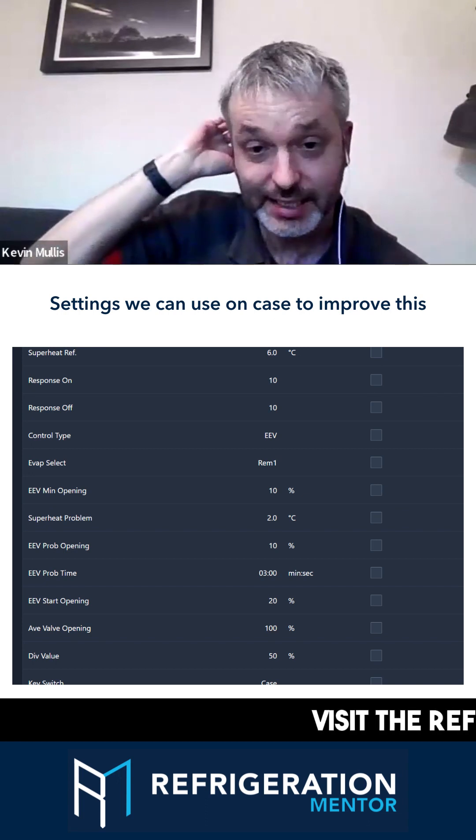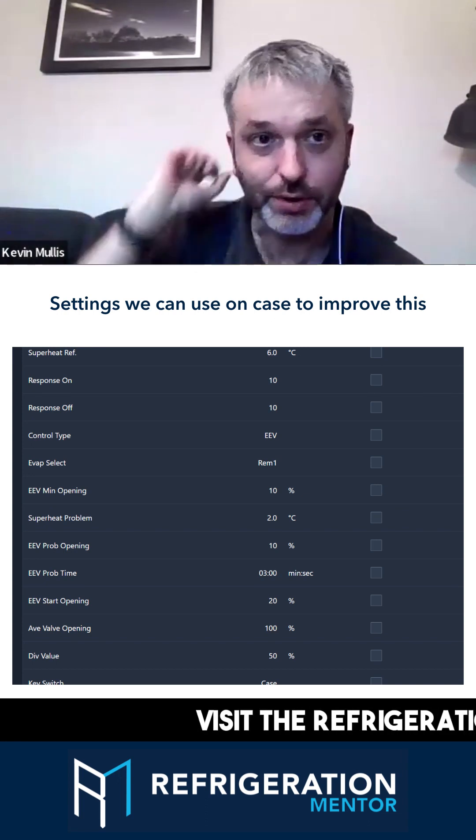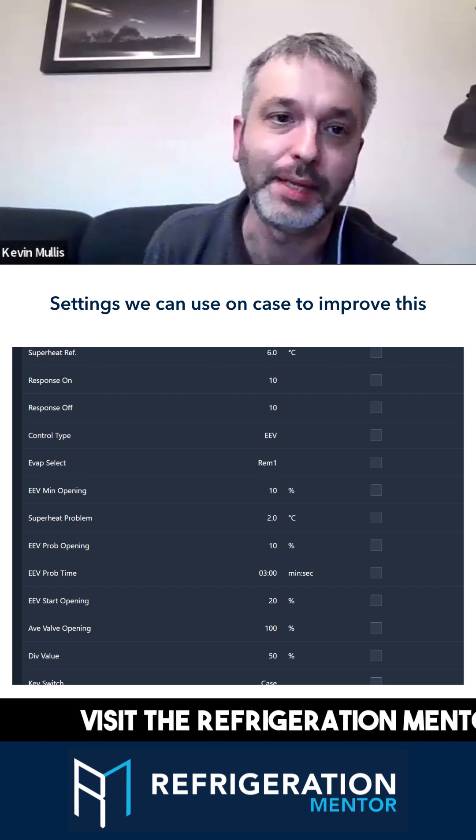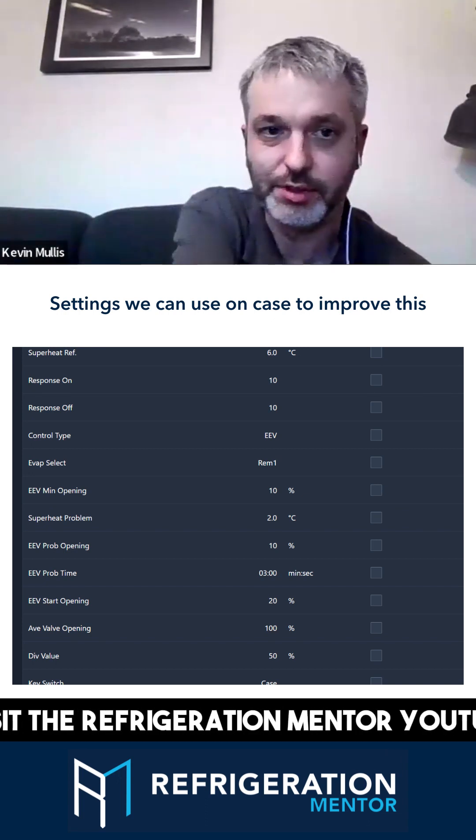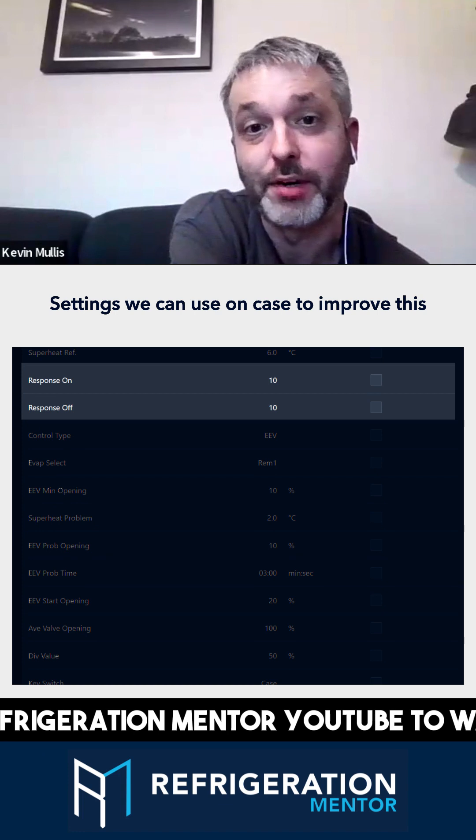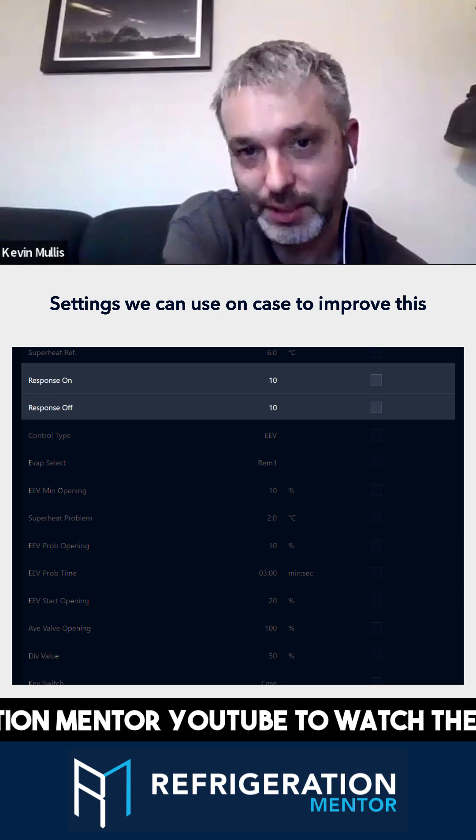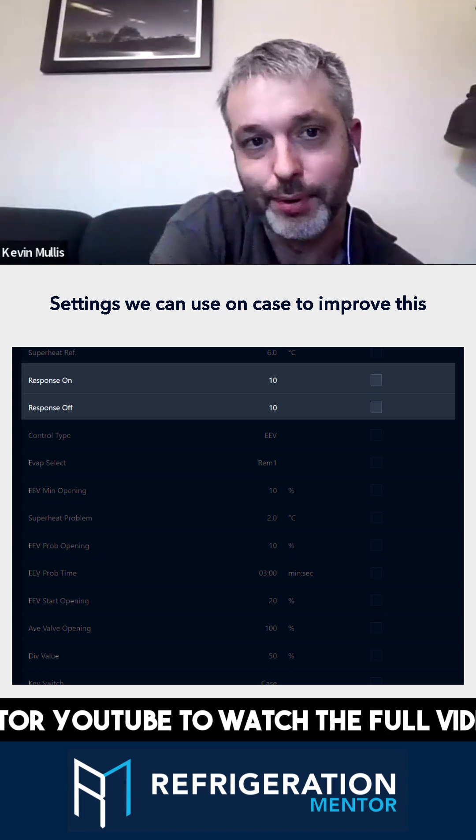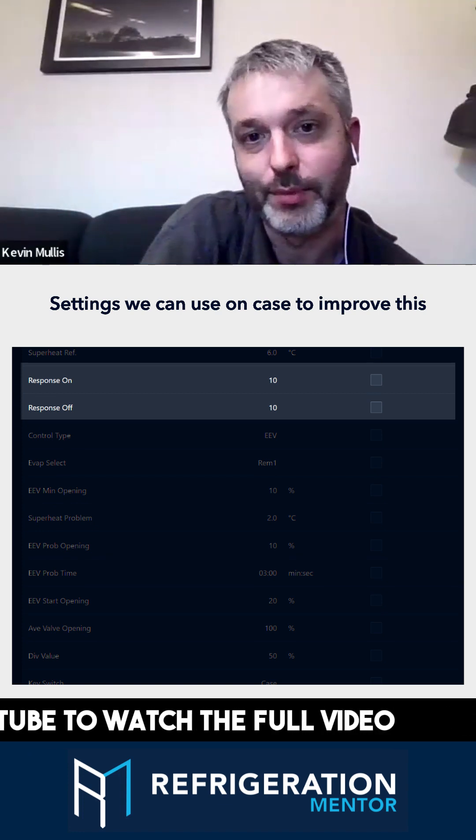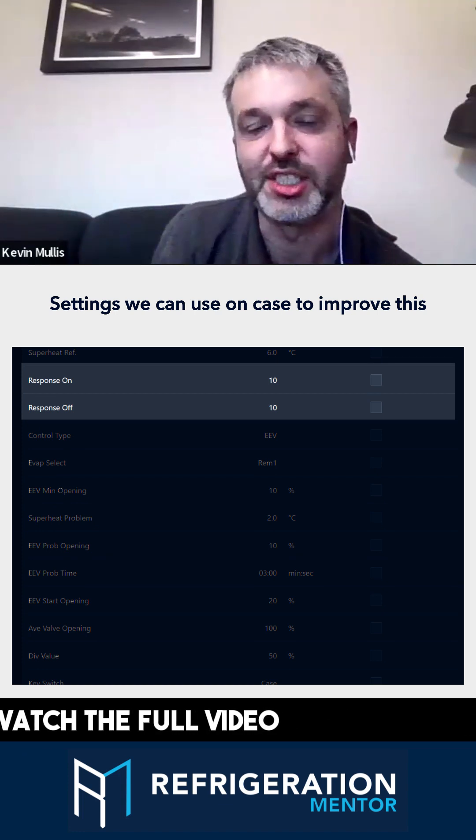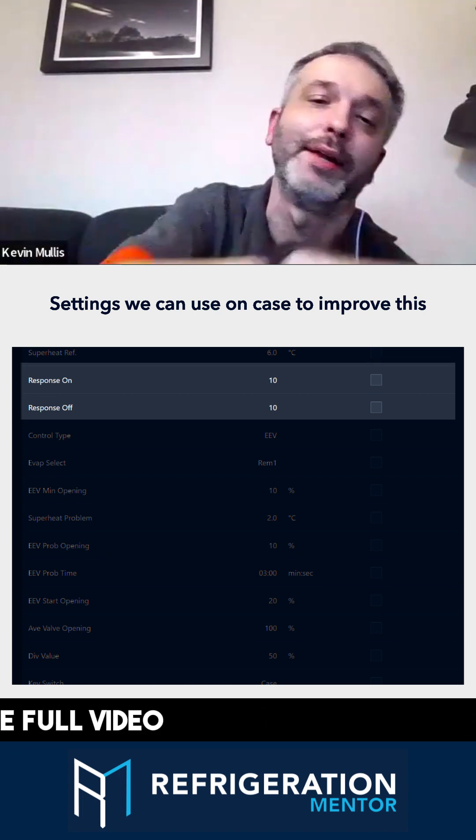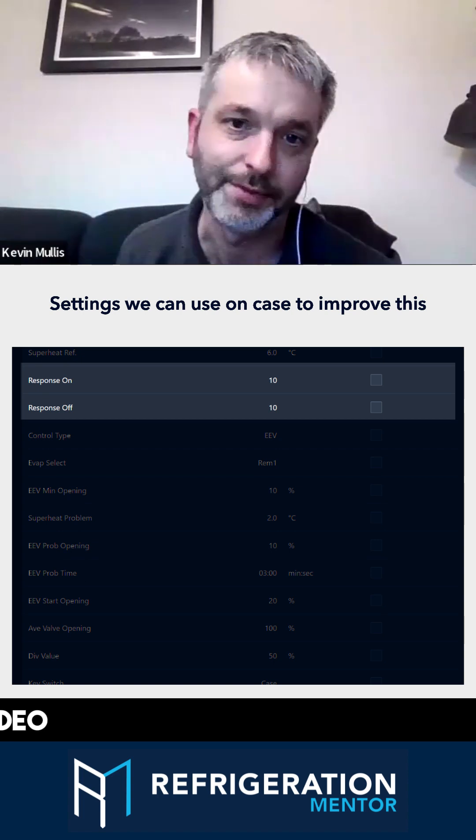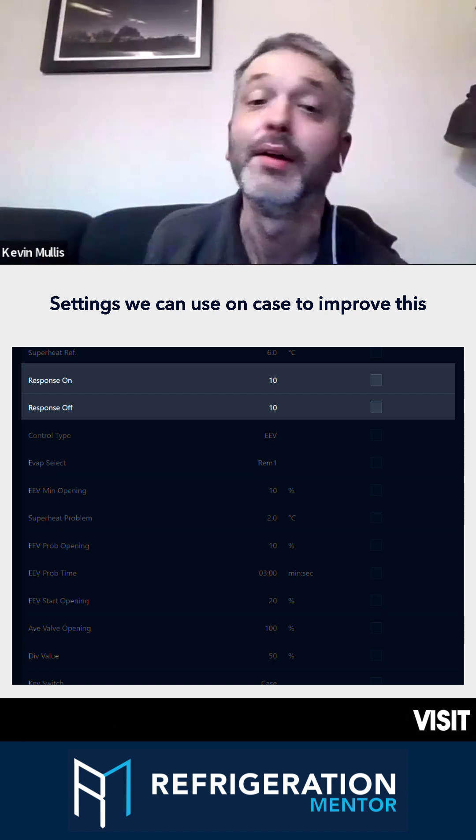On your case end of things, settings you can adjust for superheat control. As I mentioned, response on and response off. On this particular example, we've set them for 10, which is at the slower end of things.